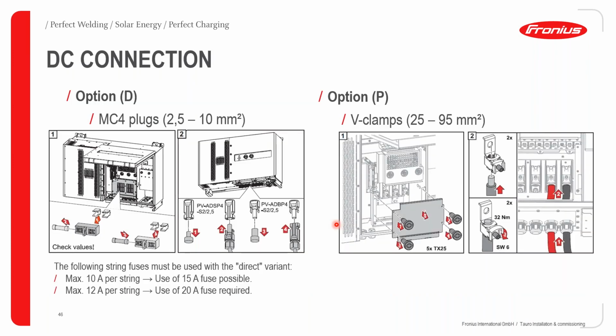For your DC connection with the direct version, okay, so D stands for direct. MC4 plugs come as standard, and they can take cable area of 2.5 to 10 millimeters squared. If you are going to have about 10 amps per string, please make sure that you make use of a 15 amp solar fuse. However, if you are going to be using 12 amps per string, please make sure that you order the Eco with the 20 amp solar fuse option. Okay, again, the reasoning for this is always suggested that your fuse should be 1.5 multiplied by the short circuit current per string.